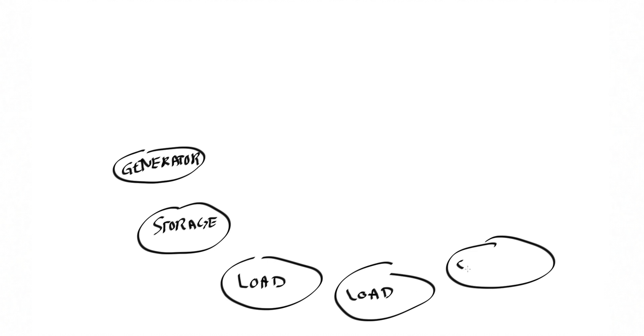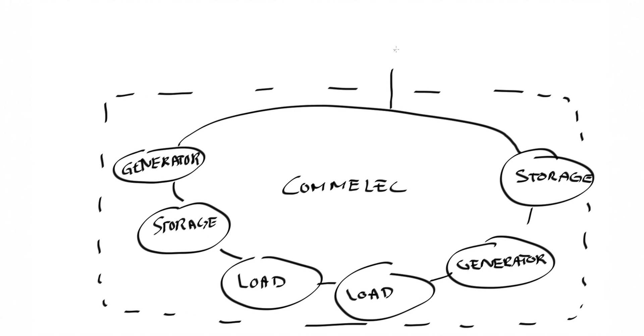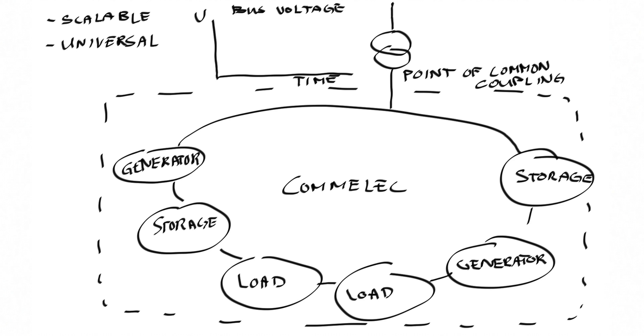COMMELEC is a framework for managing power flows in the distribution grid and works by explicitly controlling the generators, loads and storage elements in real-time. New control setpoints are computed every 100 milliseconds. The framework is scalable, as it applies to grids of any size, and universal in the sense that it supports heterogeneous collections of resources. The framework takes the constraints of the grid, as well as the uncertainties in power injections, into account.